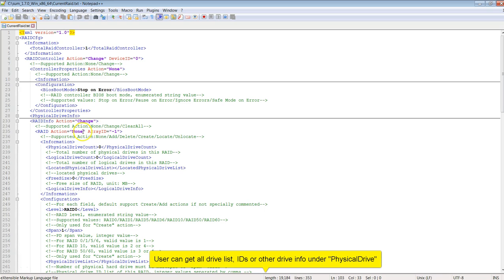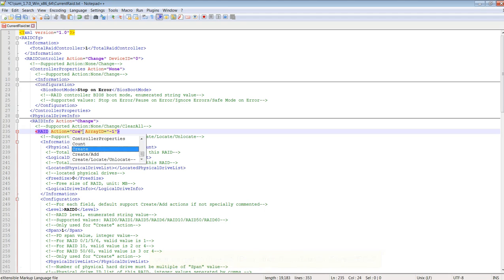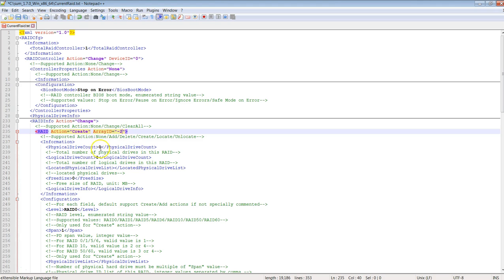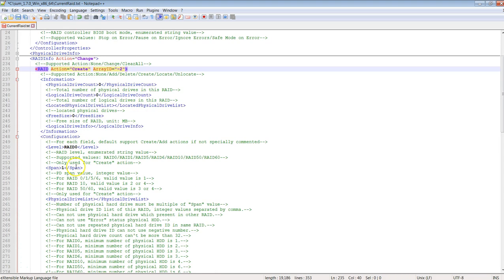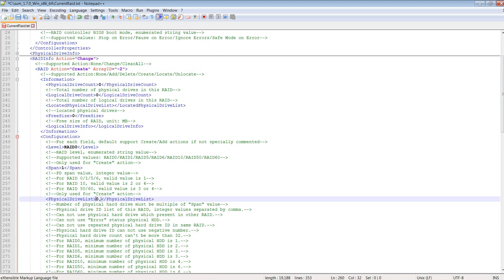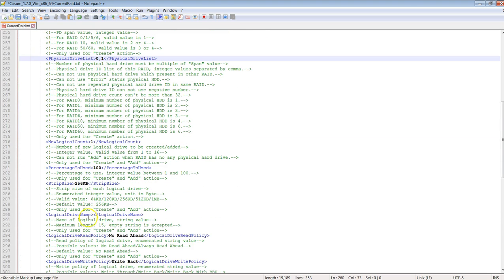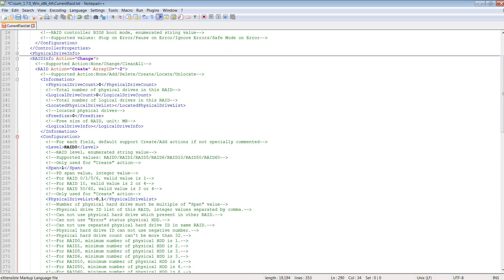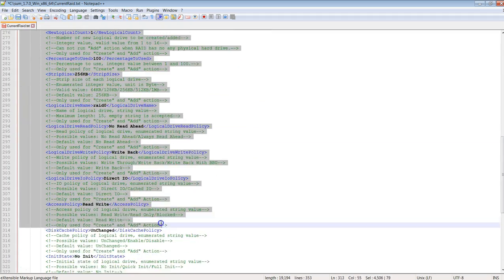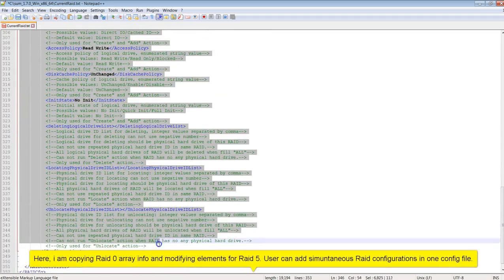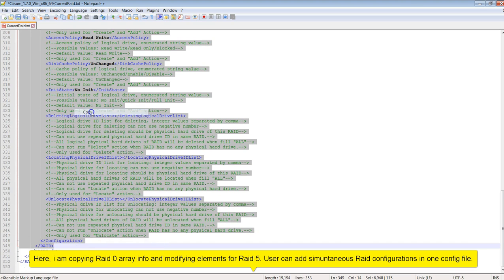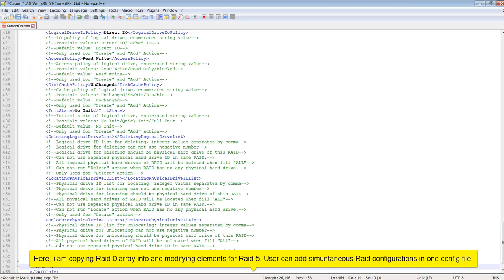Under RAID info, I'm changing RAID action to create and Array ID to minus 2, as I'm going to create two RAIDs. Then under configuration, I set the RAID level and physical drive IDs. Here I'm using drives 0 and 1, assigning them as RAID 0. Users can modify all these fields with supported values. I'm copying the RAID 0 information and modifying elements for RAID 5. Users can add multiple RAID create operations in one configuration file.